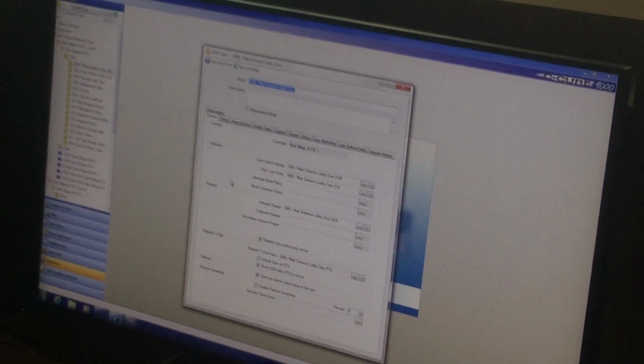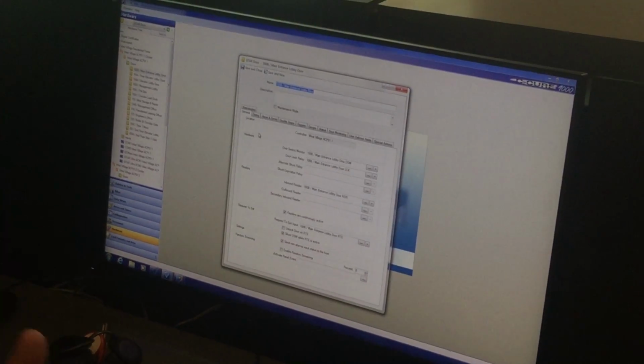What makes up a door, and this is what we program, is we create a new door and assign a door contact, a lock relay, and a request to exit. We do some shunting of the DSM, which is all normal, so that when the REX is active, the door contact is not. That way you're not getting false door held or door forced alarms.